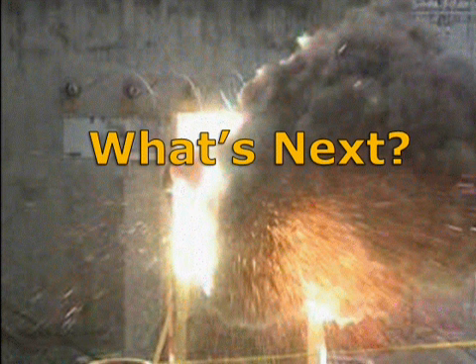The second category would be removing personnel from the arc flash boundary. Examples of that would be remote racking, remote operation, and opening and closing of the breaker, those types of operations. The third category would be reducing arc flash incident energy. That's where you're reducing the incident energy primarily by reducing the arcing duration. The three major drivers of the incident energy are the available fault current, the voltage, and the arcing duration.